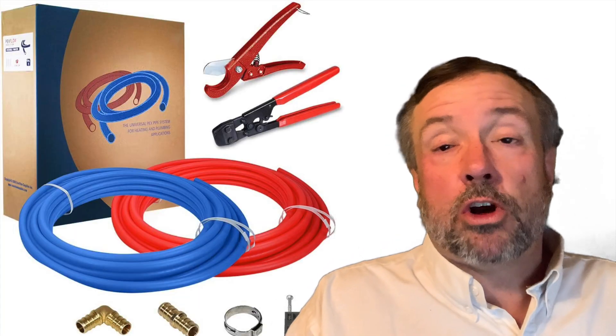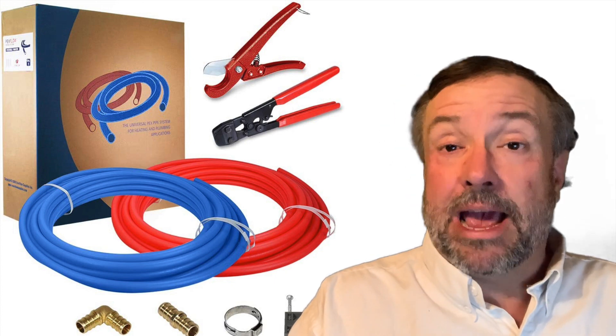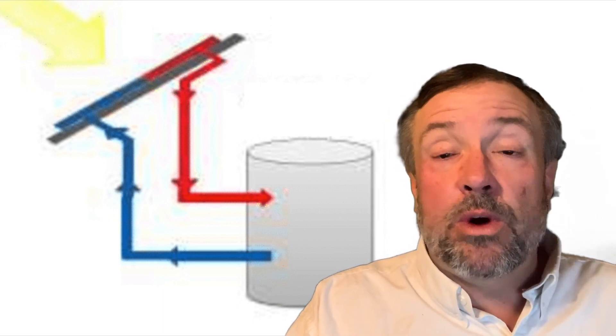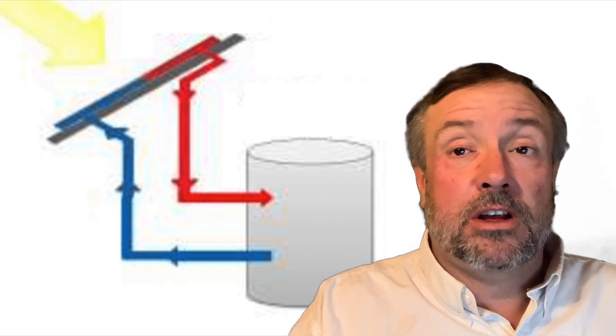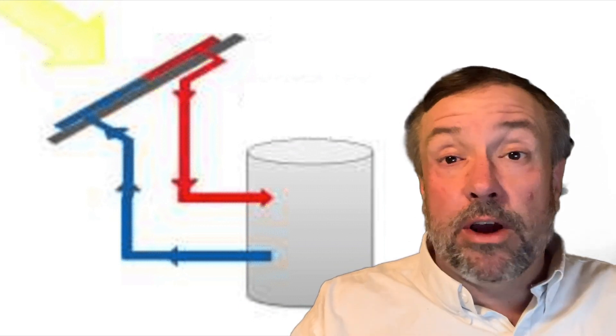The most common liquid transfer tubing available today is PEX. Now PEX is designed to handle up to about 80, 85 degrees Celsius. So if your thermal heat source goes over that, PEX becomes a little bit of an issue. But if you're dealing with lower temperatures, PEX as a liquid heat transfer tubing is very affordable.